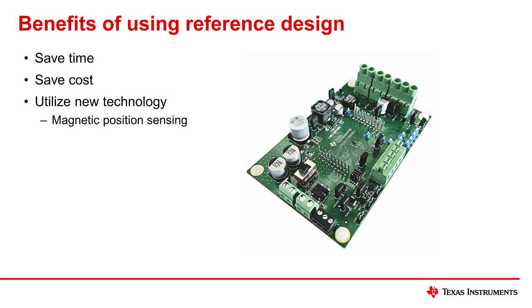It also helps improve the overall efficiency of the system due to its ability to detect if a motor is stuck in an unwanted position. For example, if your room temperature is set too low, but the damper is malfunctioning and not moving to the correct position, the controller is typically unaware of the fault and will continue to inefficiently attempt to cool the room by pumping in more air.